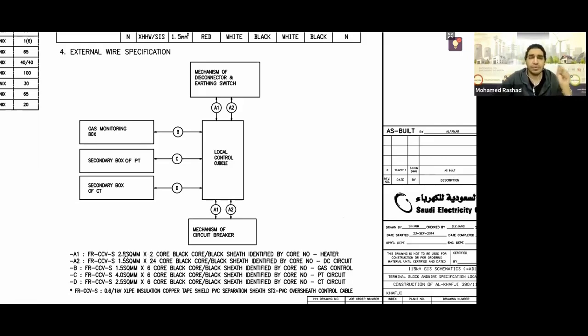Yes, because the 2-core cable, which is 2.5 millimeters, is definitely used for the heater, all right? So you'll know from where to follow it. You'll continue and you'll find, for example, the black cable here, in the end, it's a heater, and the 24-core cable, meaning 24 wires, all right? Where is this used? In DC circuits, which take, for example, the status from the breaker and then give a close command to the breaker and a trip command to the breaker and so on.